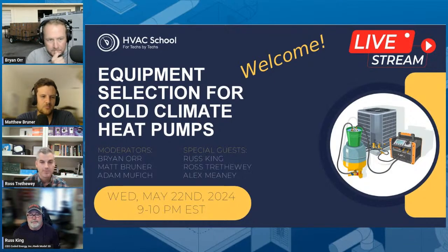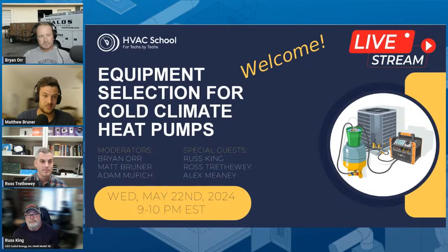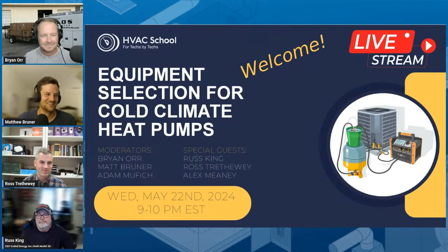Can I speak to that? So I live in Dallas, and my house was built in the 1930s, and I put in a heat pump. Went from a gas furnace to a heat pump, and it's a low ambient heat pump, and I did that probably 3-4 years ago, and very quickly realized that I knew nothing about load calculations, because I realized my heating load was even here in Dallas much higher than my cooling load. The first winter, I did a lot of silly things. I put it right on the ground. The defrost started backing up the back of the unit. I was out there with a shovel, chiseling ice off the back of my heat pump, which I do not recommend. But I mean, that's also a good place to start, is maybe your own home, because at least if you have to fix something, it's close by.